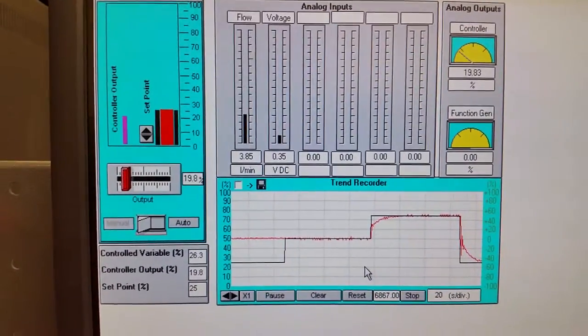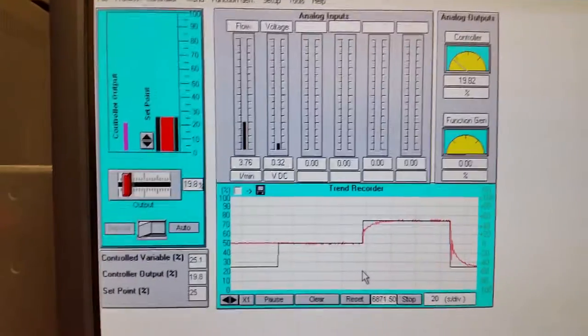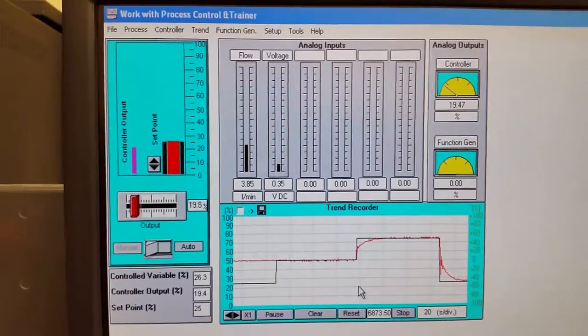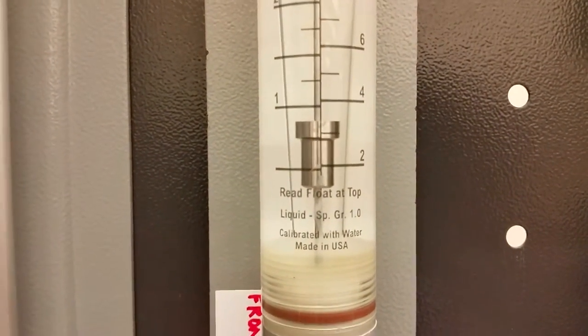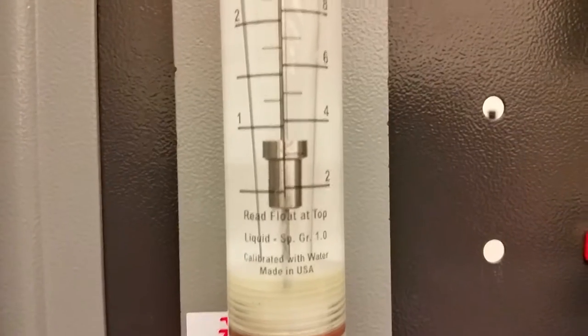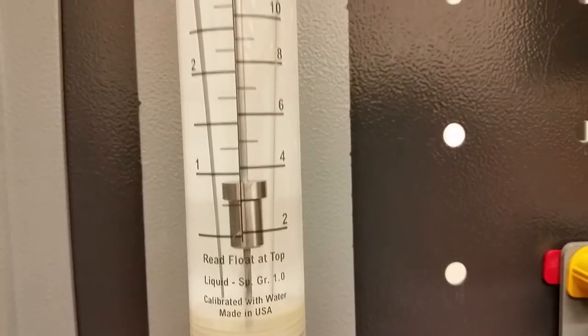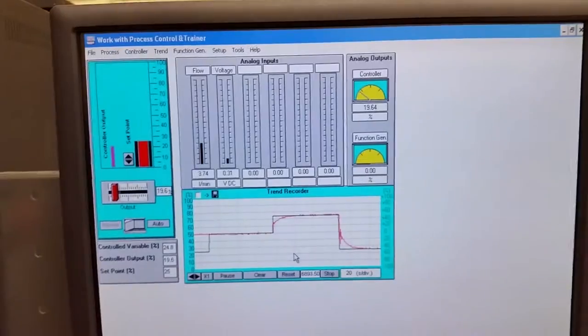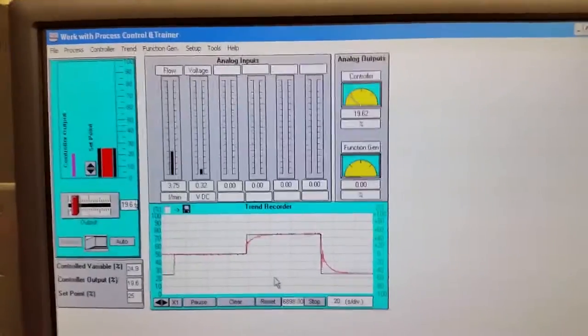The voltage is really low now. Remember at low flows the venturi tube is not that accurate. On the rotameter we're supposed to be at 3.75 and we're about 3.5 to 3.6 — not deadly accurate at low flows, better for higher flows. Half the battle is calibrating it, then tuning the parameters so it reacts properly.